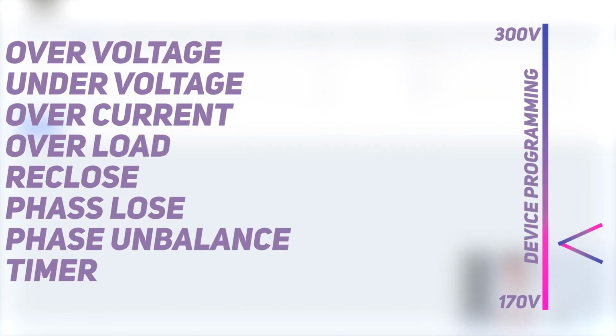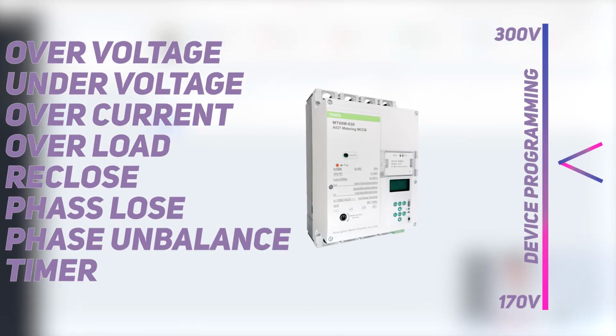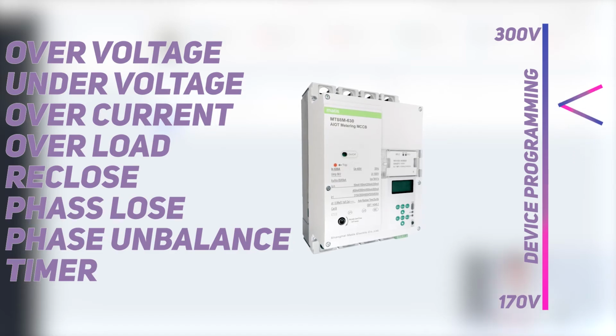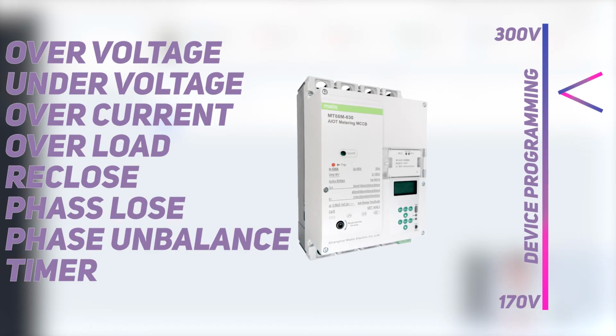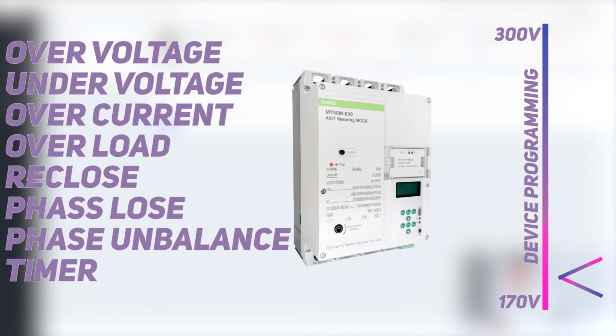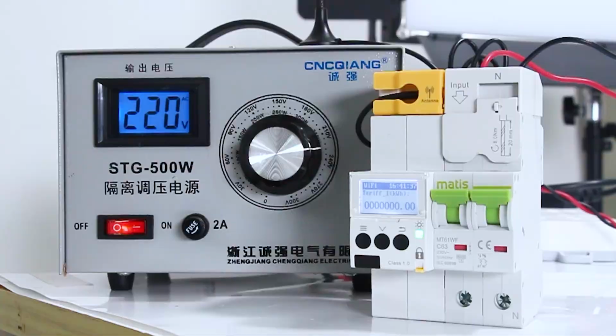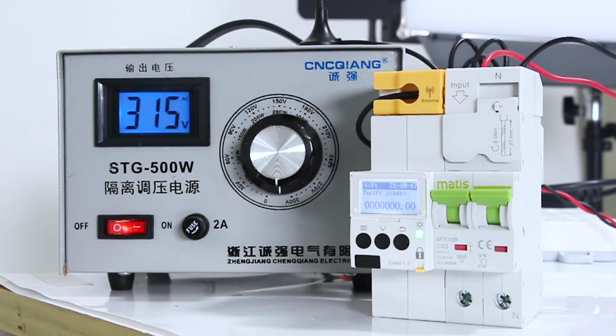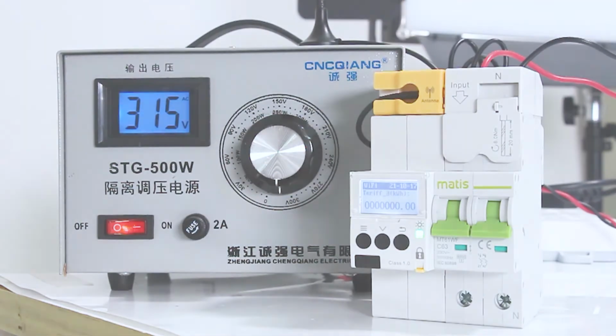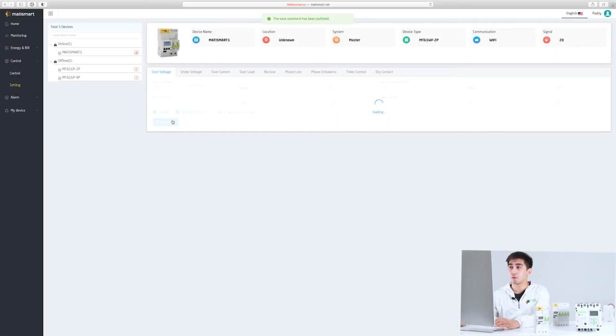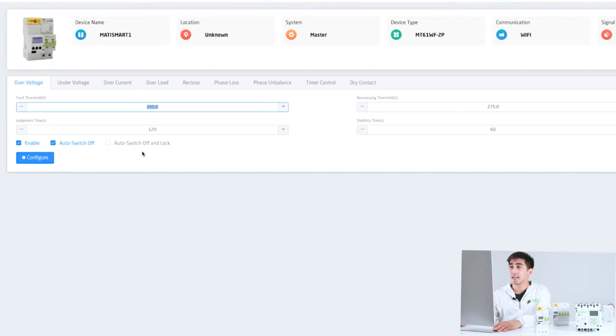Below, we have a tab with settings. Let's get acquainted with the advanced device settings. We select our device and see that we have a lot of tabs that display some numbers and tables. Let's take a look at what it is. Here we see tabs with the names of the parameters of the power grid. These calculations allow us to configure the device for a certain mode of disconnection and reactivation, that is, to program the device to work. For example, when the voltage rises to 280 volts, the device will turn off, but if we want to lower or increase this threshold, we can set some values and save these configurations.